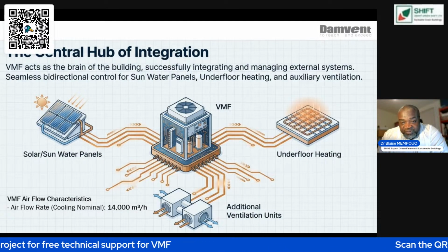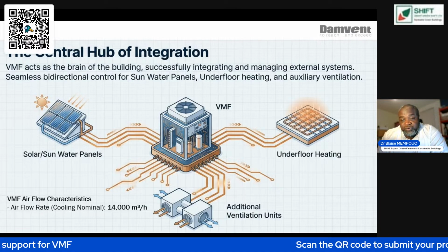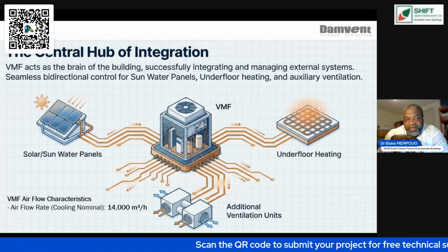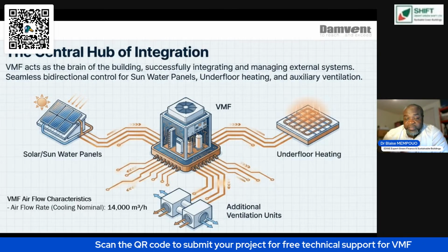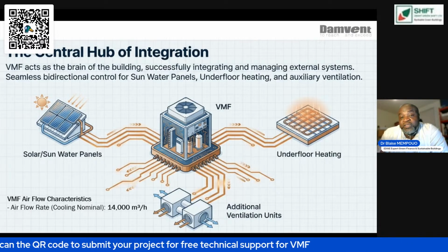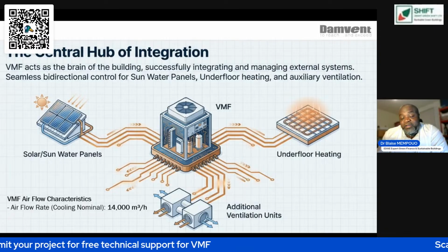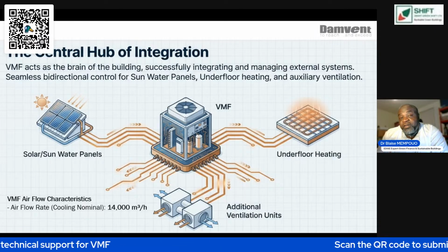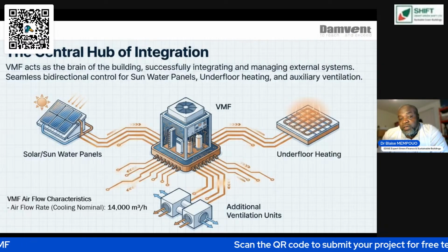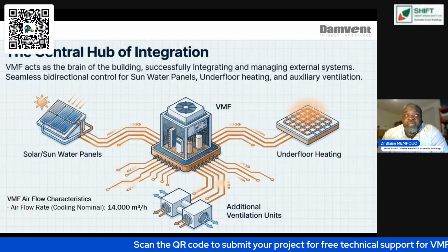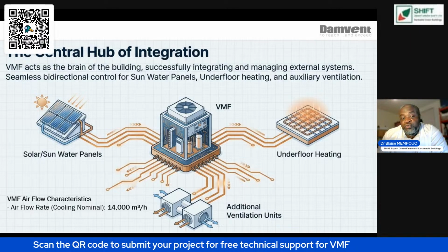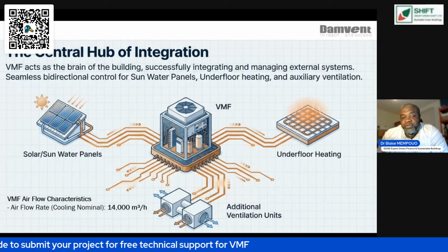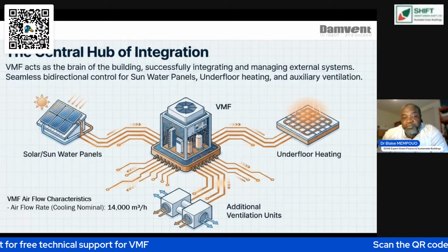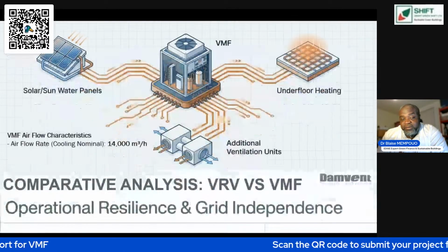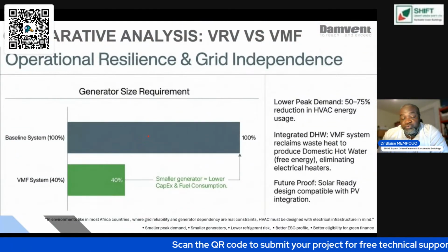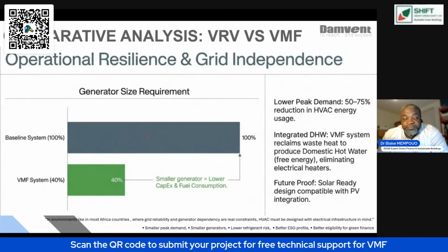So there's a possibility to integrate a solar system, because the VMF can act like a brain of the building. It's successfully integrated - if we put in a solar system, since our system relies on a buffer tank for hot water, if we integrate with the solar system and the outside temperature is good, the solar will be prioritized over the compressor. The compressor only works if the solar outside is not sufficient to do the job.